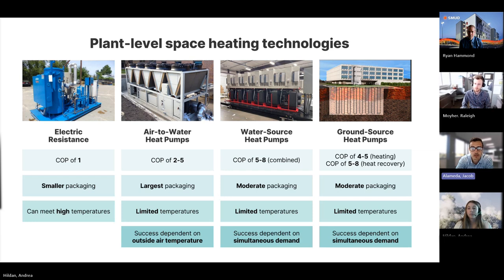Air-to-water heat pumps also have the opportunity to be 2-pipe or 4-pipe machines. 2-pipe machines can produce heating water or chilled water, but not at the same time. But 4-pipe machines can simultaneously produce heating water and chilled water, and they can do heat recovery. So if the heating load and cooling load isn't balanced, the air can be used as an additional source to either pull heat from or dump heat into. And that is what allows your air source heat pump COPs to get up to like 5 and sometimes even higher than that. We have a slide specifically on heat recovery coming up.